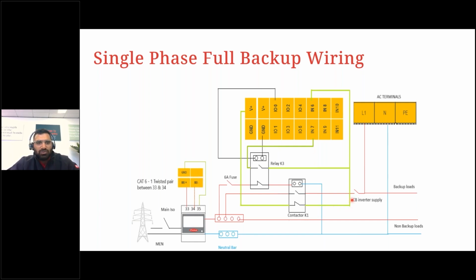So what we do is we also take a connection going straight from this normally closed towards the normally open side of the relay, and we connect it to the IN7, which is feedback from the relay. So when we have the feedback already coming at IN6 from the contactor, the inverter is like, okay, I have feedback from the contactor, it will then power supply the relay. So this normally open will now close when it is power supplied, meaning this 12 volt coming from this V+ can now reach IN6, and at the same time it goes through here and reaches IN7.